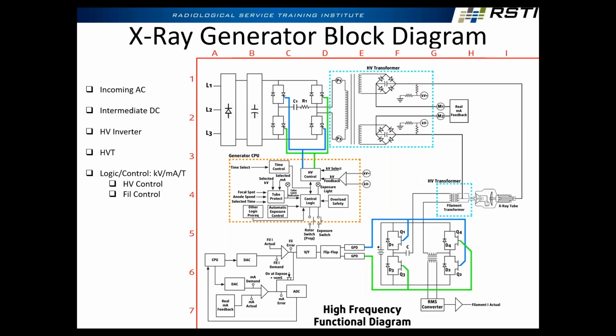And what's the job of the high voltage transformer? Step it up. Yep. Step it up to whatever kV the customer asks for. And does it make sense that if it's a 100 kV exposure, you'd have plus 50 and minus 50 here, right? Any X-ray system in the world works like this. A dental unit, a GE rad room, Philips CT. If it makes X-rays, it's going to do this exact same thing.